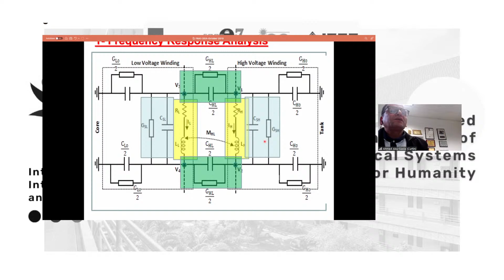You know, in a transformer, we have first the core, then the low voltage winding, then paper insulation and oil, and then the high voltage winding. So between the low voltage and high voltage, we have mainly paper insulation, and oil going in ducts, which can be represented by capacitors and conductors. Between the low voltage winding and core, when we wind the transformer, we start with the core, then the low voltage winding. But between them, of course, we must have insulation, that's varnish on the laminated steel, and paper insulation. Again, any insulation can be represented by a capacitor. And all of these windings are immersed in oil. So the oil can be represented by a capacitor and dielectric conductance. So that's the equivalent circuit of a simple disk or turn.